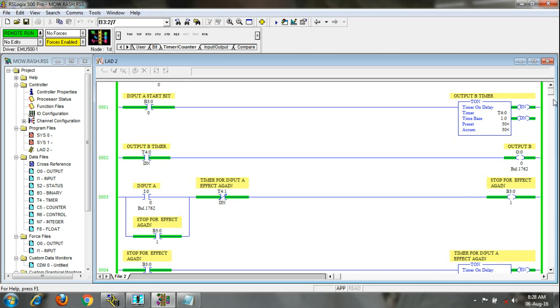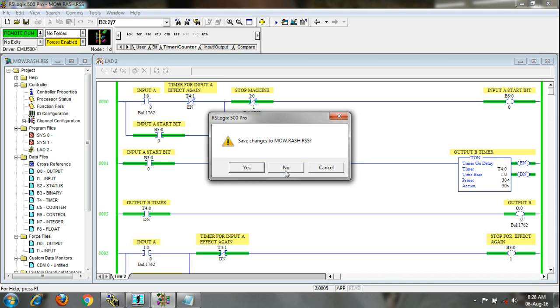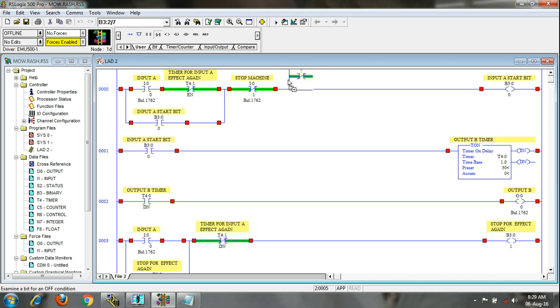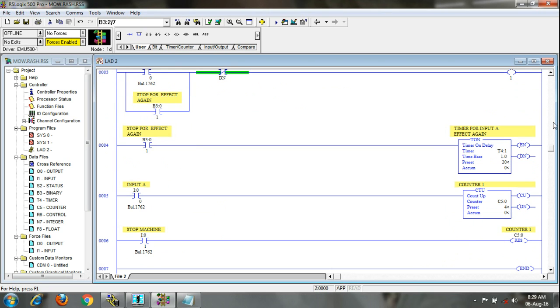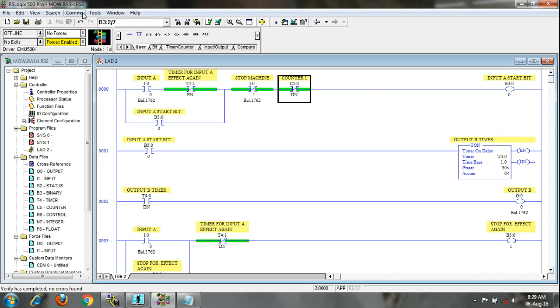Now the third part — if you press three times: one, two, three — the output should turn off. But why is it not off? I forgot the reset over here — I have to give the NC of that counter here. I have to give one reset. The address of the counter is C5:0, so C5:0/DN — this will reset the counter.